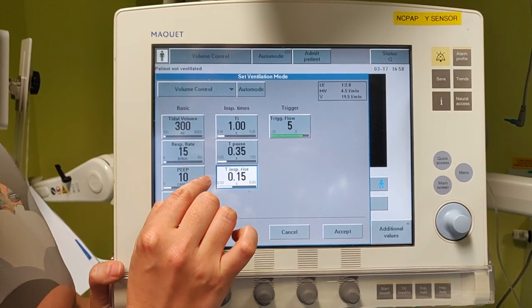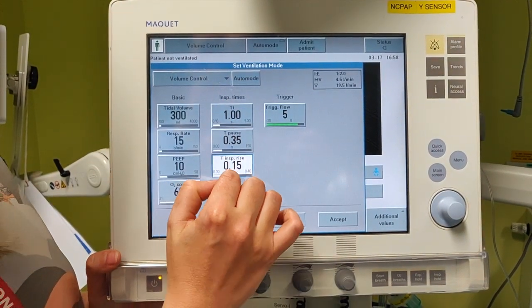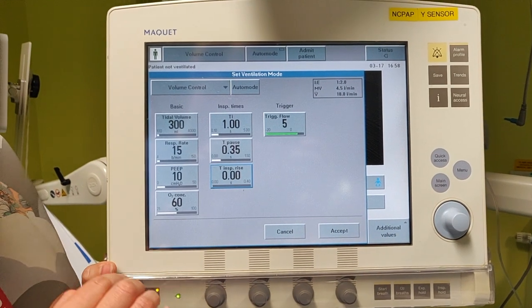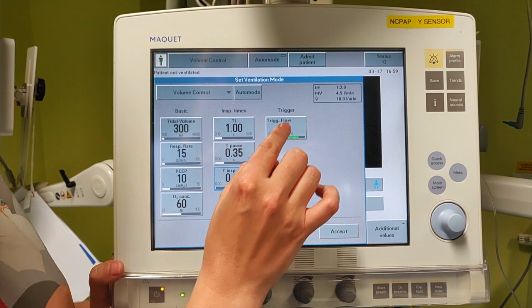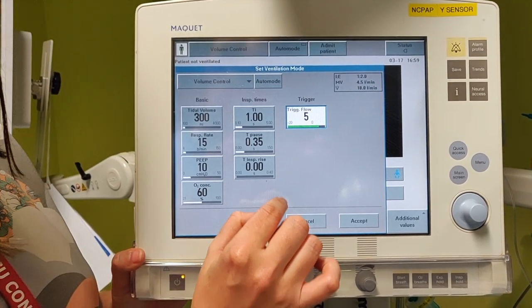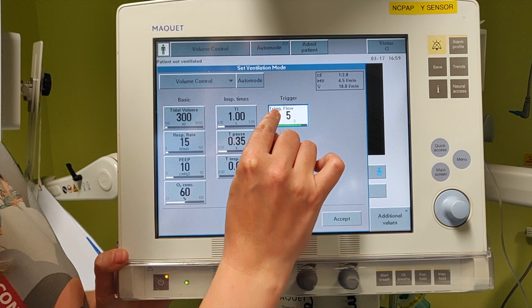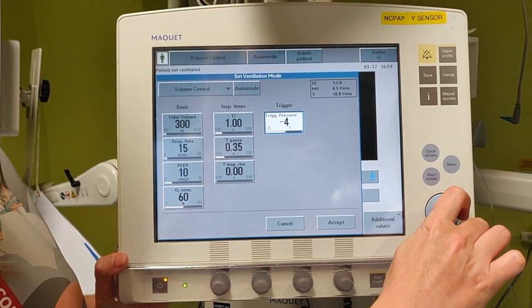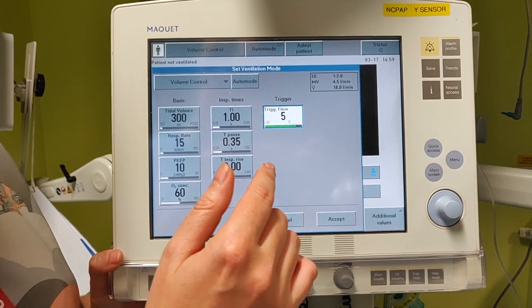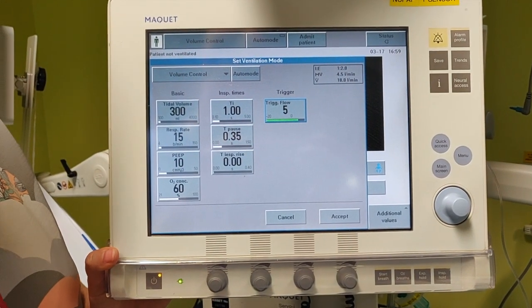What is this rise time number? This is how long it takes for the ventilator to come up to full pressure — it slows the delivery at the beginning. This is not necessary, and definitely not in volume control. You want the air to go in at a constant rate; you don't want any delay in delivery. So you can set that at zero. Then we have the trigger — this is how the patient activates the ventilator, which at the very beginning isn't going to be necessary, but when the patient starts waking up, you want this trigger to activate the breath when the patient wants. There are two types of triggers in this ventilator: flow trigger on the right side and pressure trigger on the left. We're going to set up the most sensitive trigger that doesn't make the ventilator auto-trigger — activate without the patient wanting. We're going to leave it at five. So these would be the basic settings in volume control, and I'll see you in the next video.